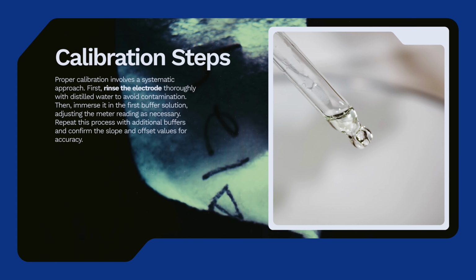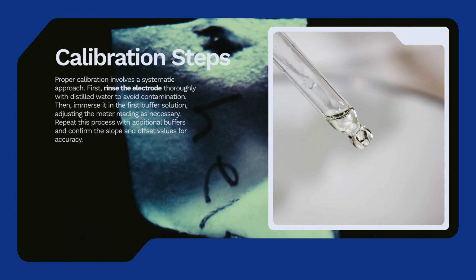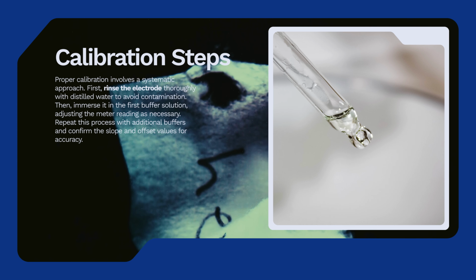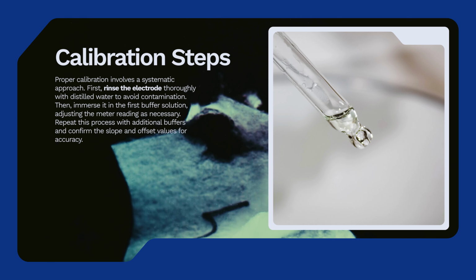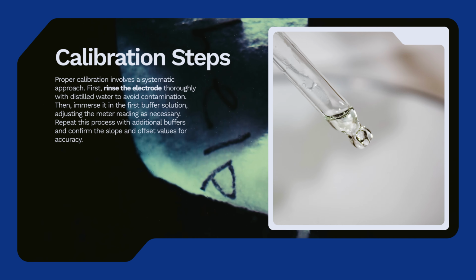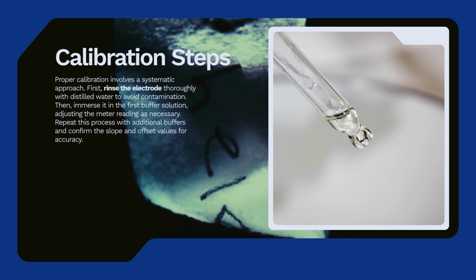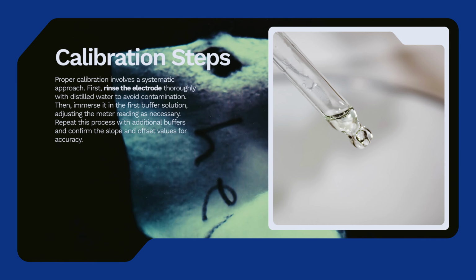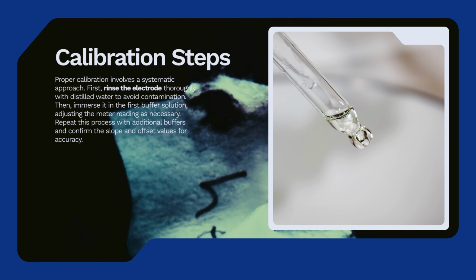First, carefully rinse the electrode with distilled water to prevent cross-contamination. Immerse the probe in the first buffer and adjust the meter reading accordingly. Then, repeat this process with additional buffers to confirm the electrode's slope and offset values, ensuring linear accuracy across the scale. After the calibration is complete, always measure a standard buffer to verify the final precision of the system.